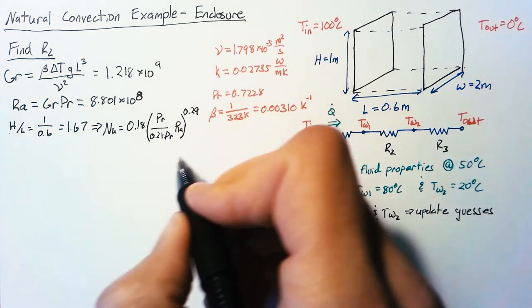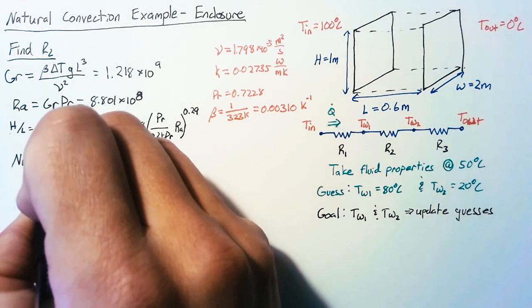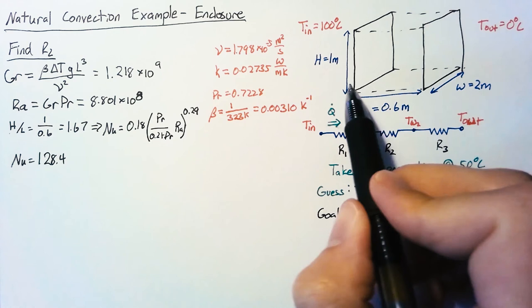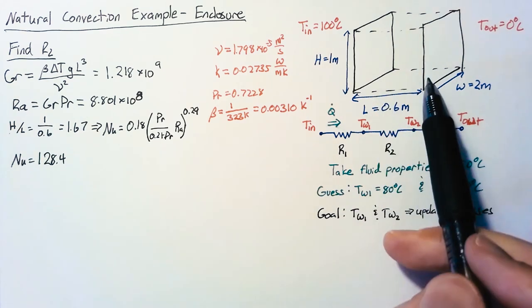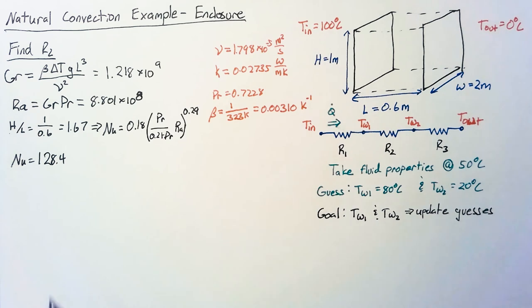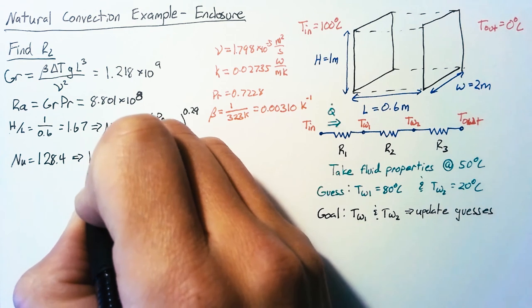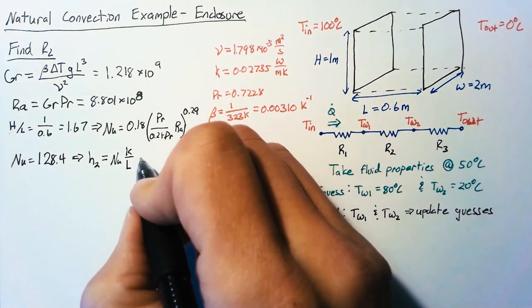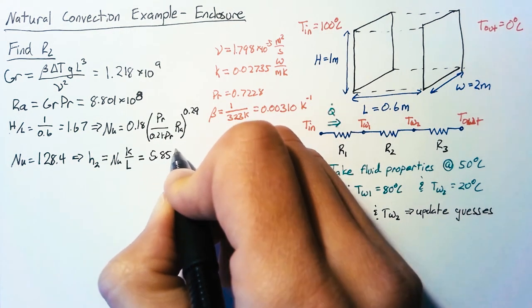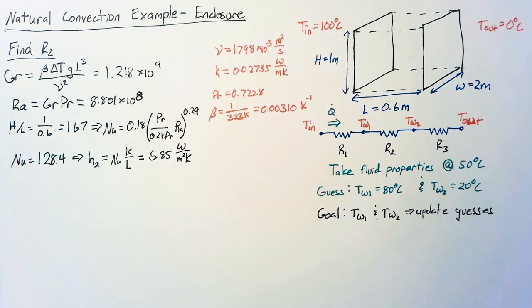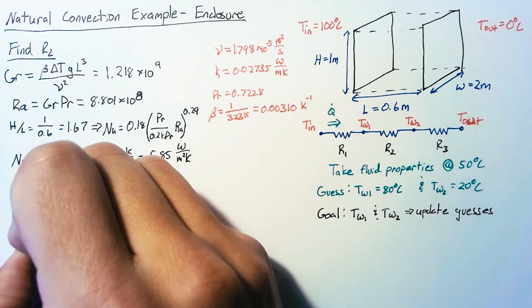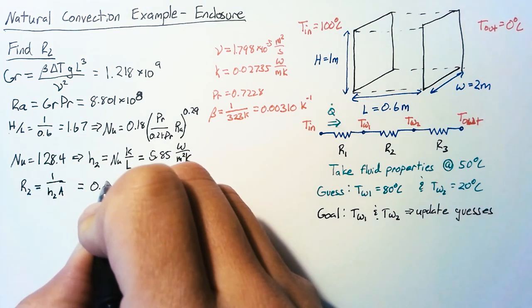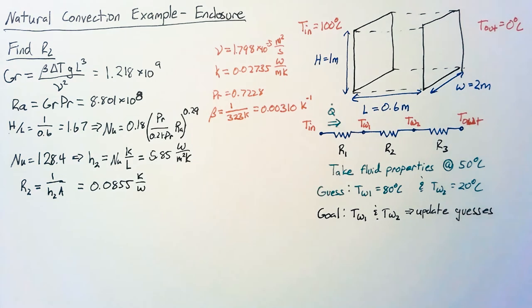So using this equation we can plug in our values and we get that the Nusselt number is 128.4. So for this large enclosure the heat transfer rate is 128 times what it would be for still air. That makes sense because there's a lot of room for the air to move around in there. Using the Nusselt number we can go ahead and calculate our heat transfer coefficient which is just Nusselt number times k divided by L and that's going to be equal to 5.85 watts per meter squared Kelvin. Finally we can get to our R2 value by taking 1 over h2a and that ends up being 0.0855 Kelvin per watt.